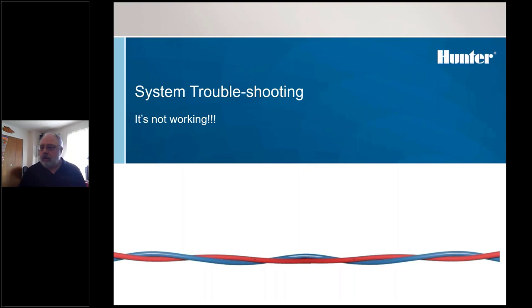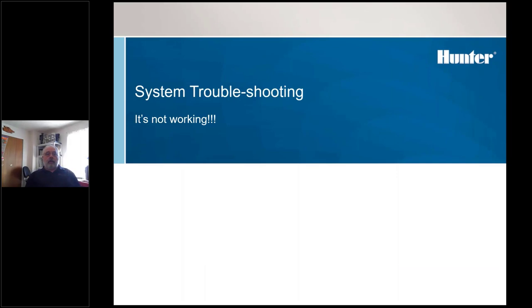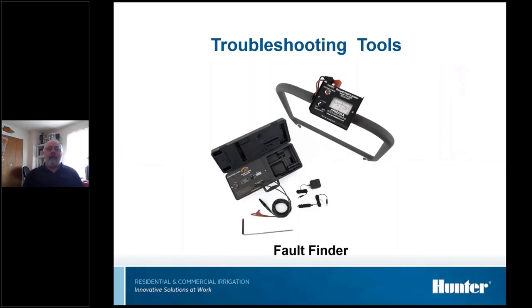Hey, Dave, I got a question on the fault finder, if you got a second. Sure. Is it safe to use that tool on our decoder systems? Should they disconnect the decoders on the path before they use the fault finder? What's our recommendation for that? You should disconnect. If you're using a fault finder, they induce tremendous current into the ground, and it can damage decoders. For a short time period, they seem to survive it, but for the long term, you should get rid of it.